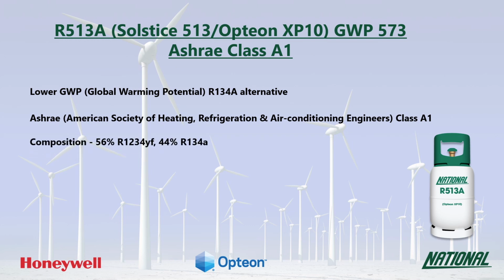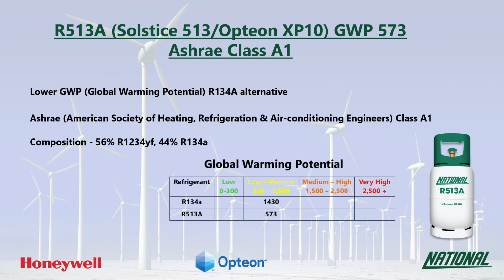R513A is a two-part blend consisting of R134A and the HFO R1234YF. With a GWP nearly a third of that of R134A, it is still regarded as low to medium, and so is not considered a long-term replacement.